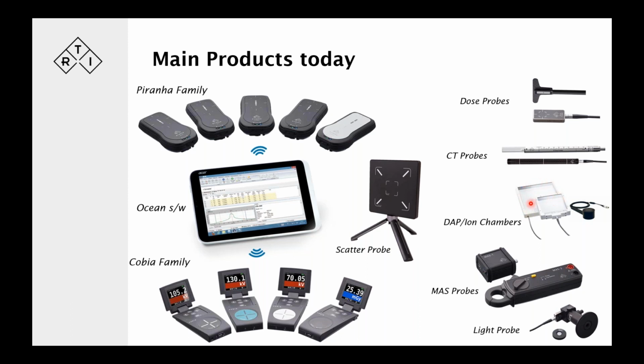There's a larger one here that fits into the normal rails in the collimator in a normal RAD tube, so that you can actually check the built-in DAP chambers that are fitted in many cases in situations like that. So the DAP chambers can have 2 calibrations, one for entry dose and another one for exit dose, so that we can determine the calibration and the readings and verify the readings on the built-in DAP chamber, if that's necessary.